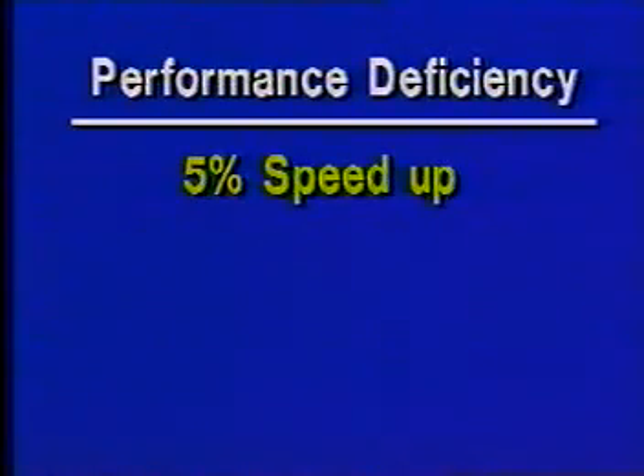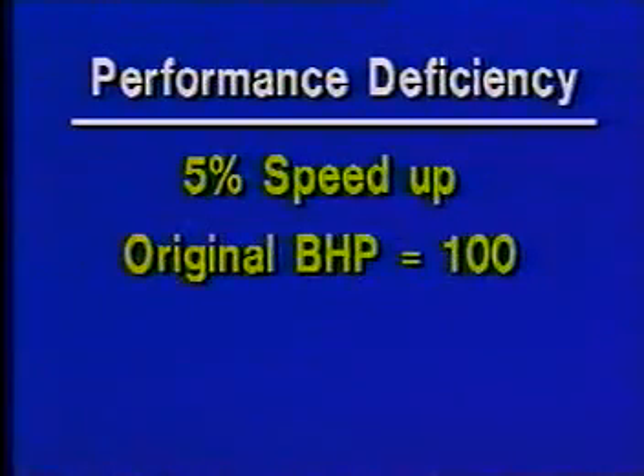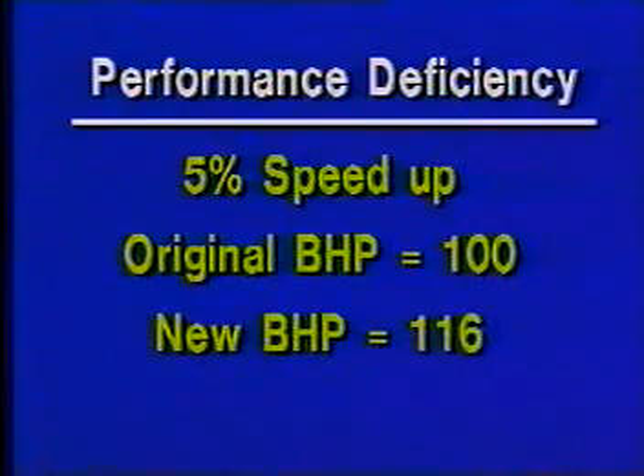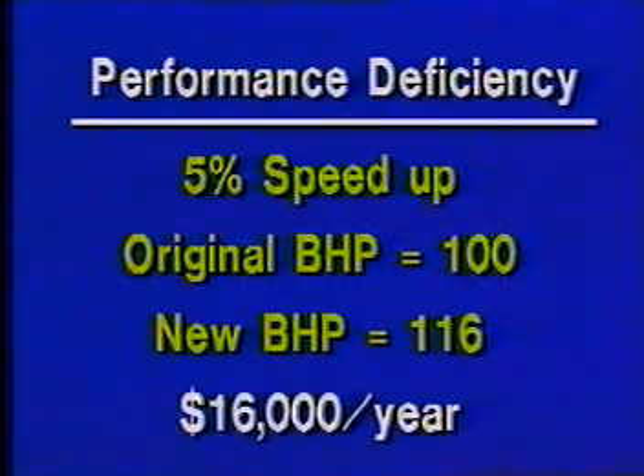Each additional unit of horsepower costs about $1,000 per year. Clearly, system effects can be a big drain on profits. Deficiencies in airflow are usually overcome by increasing fan speed. But consider this: a 5% speed up of a 100 horsepower fan causes brake horsepower to rise to 116. That increase results in an additional energy cost of $16,000 every year throughout the life of the fan.